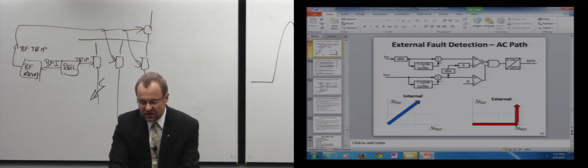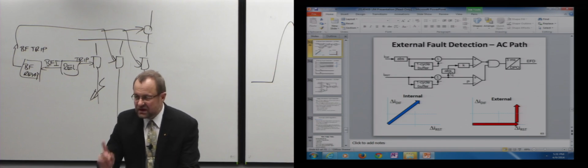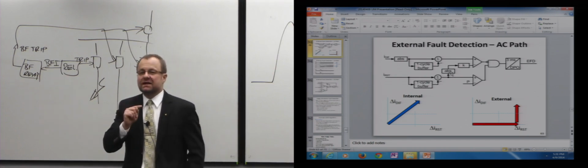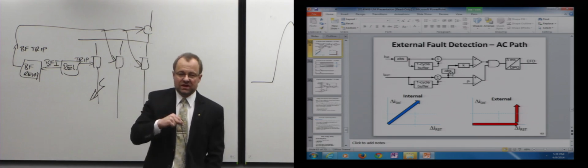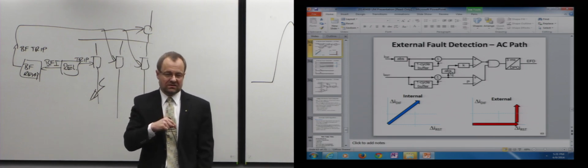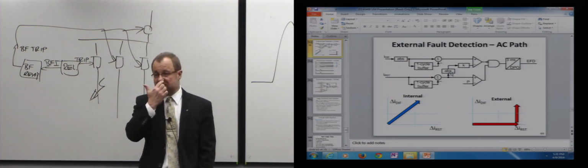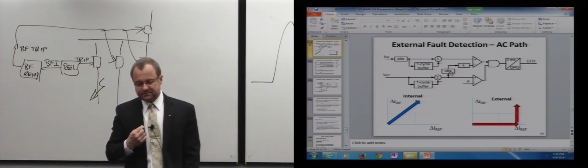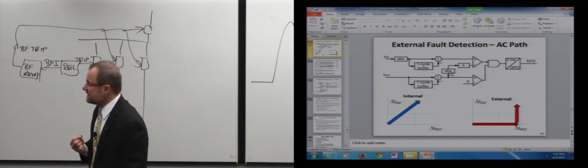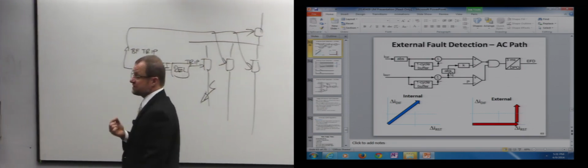This is logic 1, so it's logic 0 here. This timer will never engage. So this thing will not pick up on internal faults even if I have a saturation during an internal fault. So it's truly an external fault detector. It tells me after 3 milliseconds, you are dealing with an external fault.